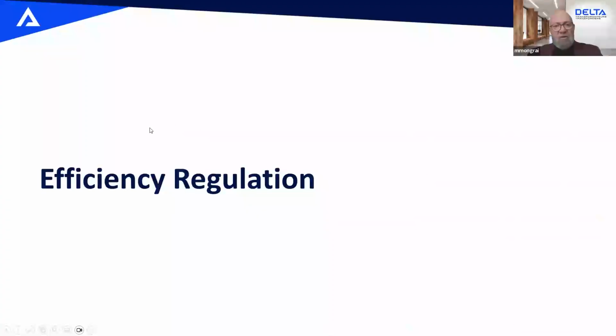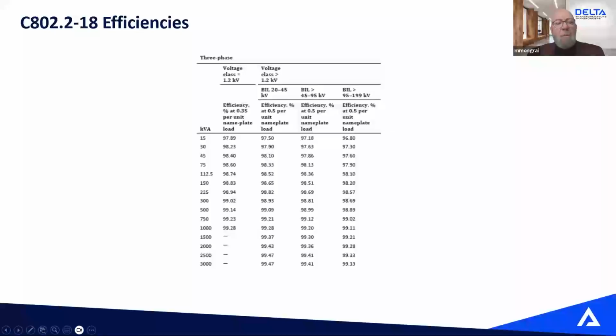A little bit about efficiency regulation, because that's kind of the base of any transformer, and I would say the purpose of generating green energy is to be efficient. In Canada, we have NRCan, that's the federal government. So it's a federal law that transformers shall have a minimal efficiency. And we use CSA C802.2-18, which is the current edition, to determine the efficiency requirement for each transformer, depending on your KVA and your voltage class, from 1.2 kV all the way up to 200 kV. As you can see, the more you go up in size and voltage class, the more efficient you have to be.